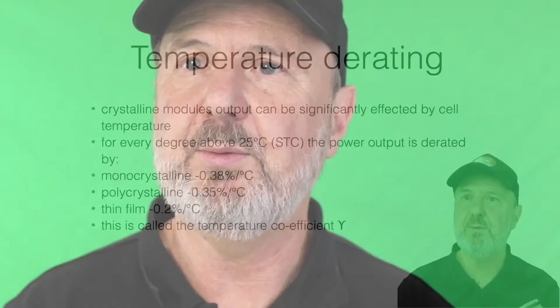You've got to allow for this in real world conditions, that the solar panel will actually produce less power under normal operating conditions, unless you're lucky enough to live somewhere that's below zero most of the time. That temperature derating is given in percentage per degree Celsius above the test conditions. You're losing around 0.4% per degree Celsius above 25, which is the test condition.